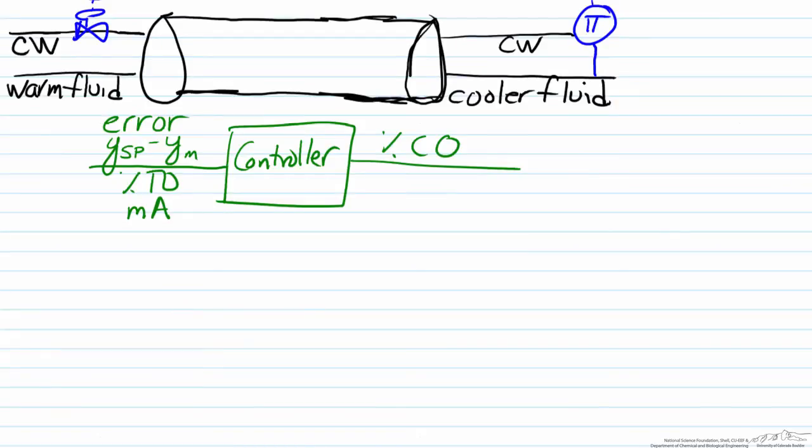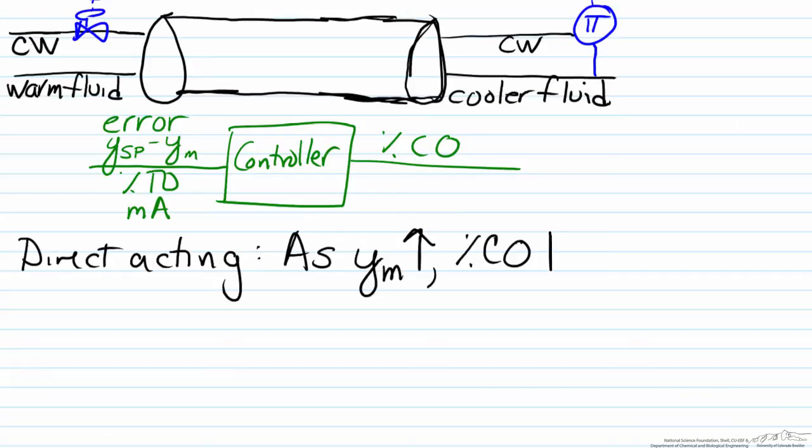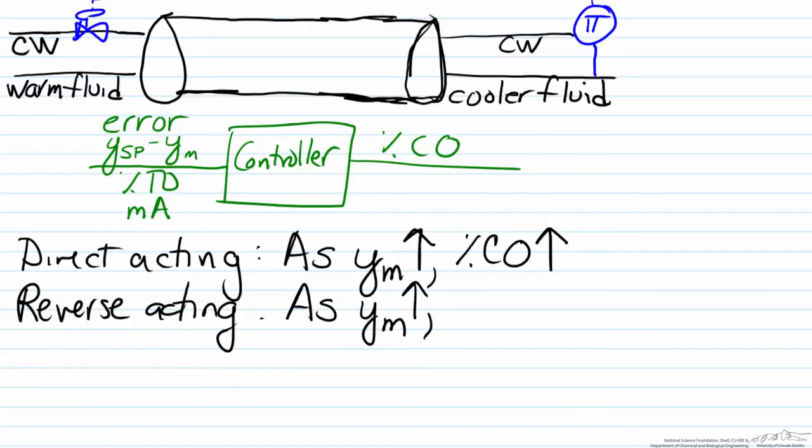Controller action can be reverse acting or direct acting. For a direct acting controller, as the value of the measured variable goes up, the percent controller output that the controller will make will go up, as the name direct acting indicates. The other type of controller action is reverse acting. Unsurprisingly, as the measured variable goes up, the percent controller output goes down.